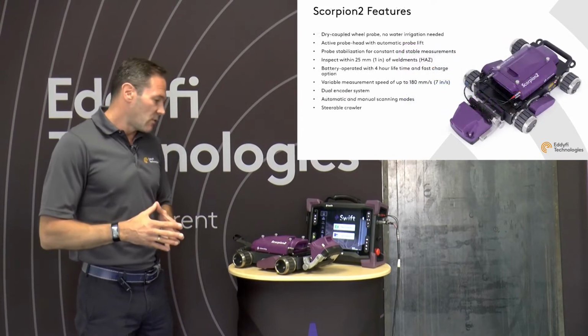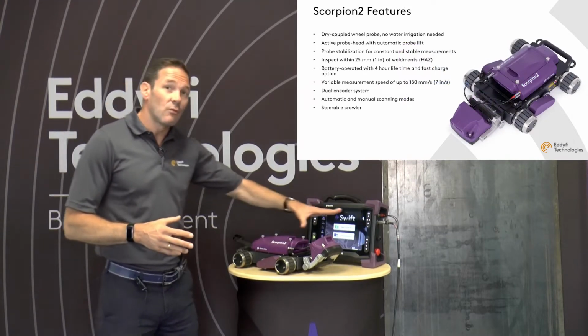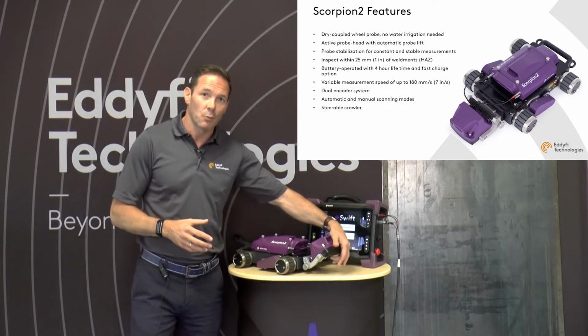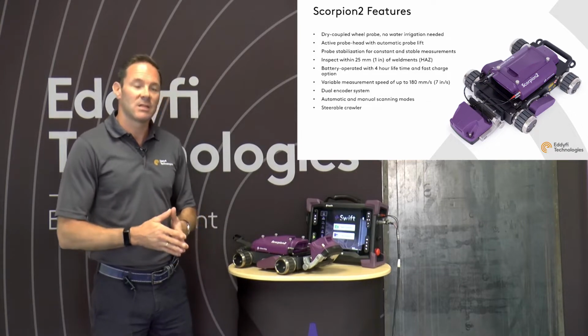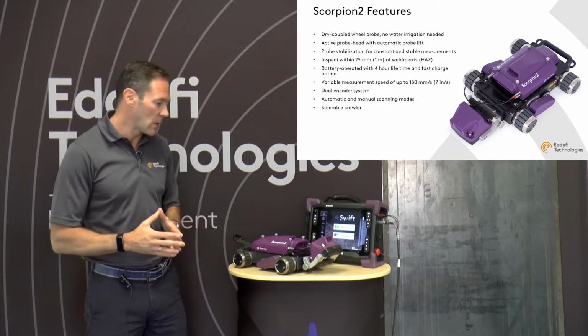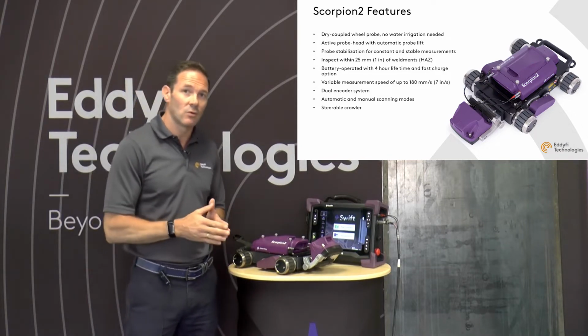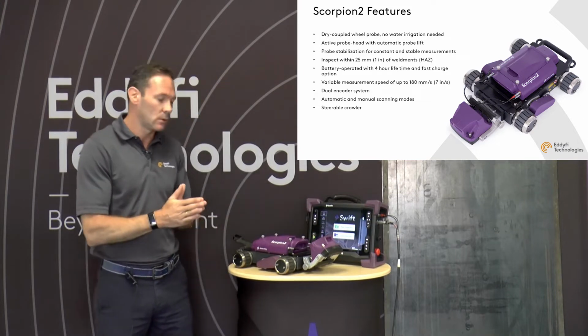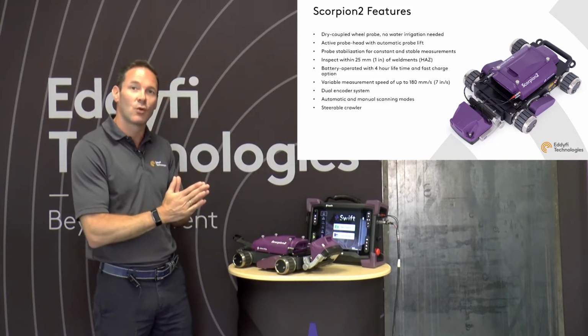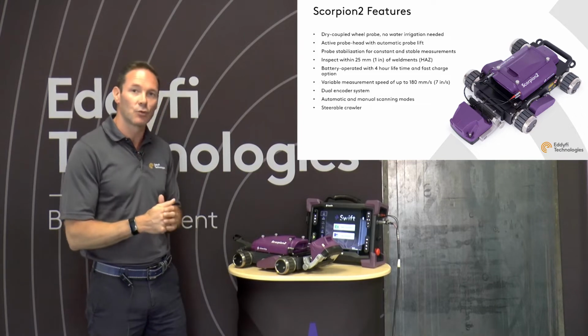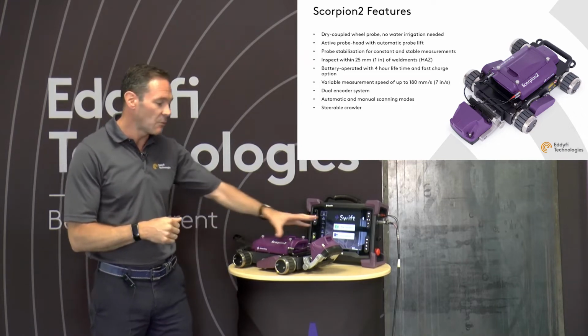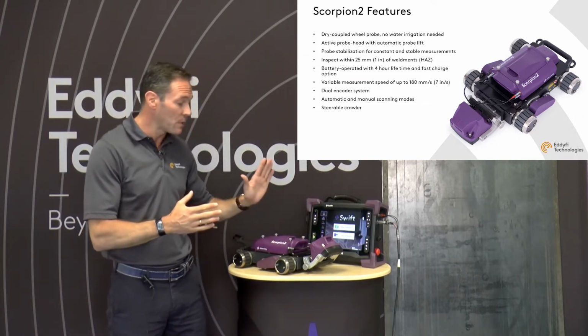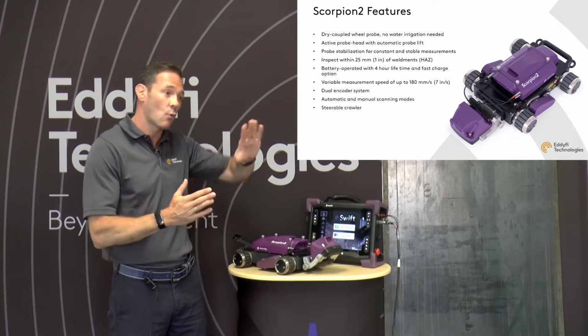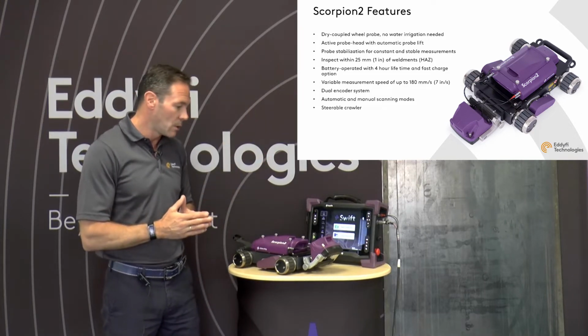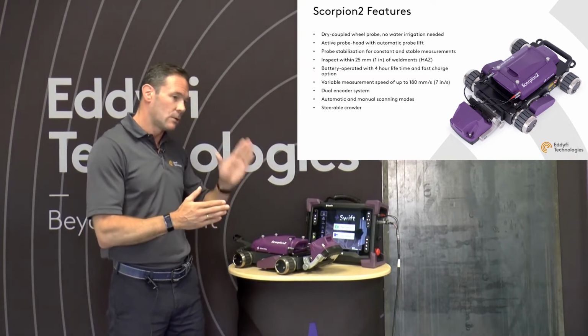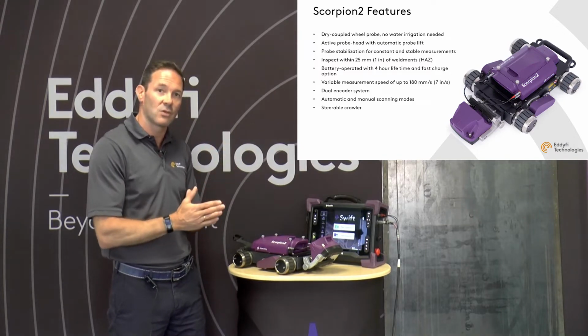Let's have a look at the Scorpion features. Well, first of all, we said that we have a dry coupled wheel probe. Nice thing about that is that you do not need water irrigation, so there's no carrying around of water. The probe will use a slight bit of oil and a dry coupled probe to actually get the ultrasound into the material. It has an active probe head where the probe is automatically lifted off the surface. So whenever we do a maneuver with the unit, the probe head is not connected and it prevents wear.